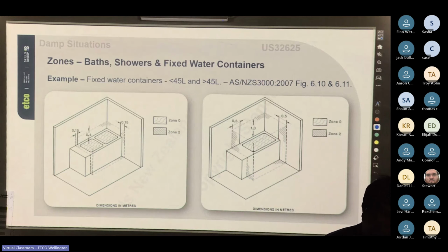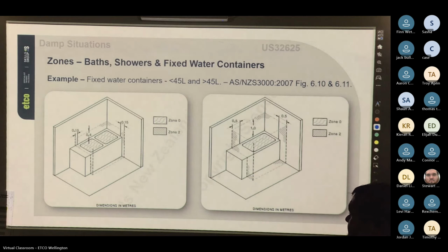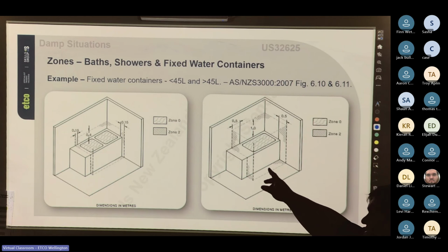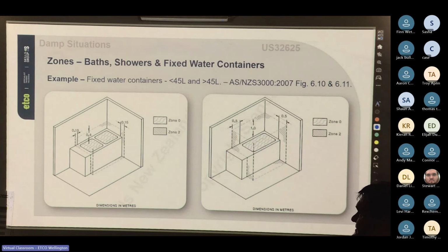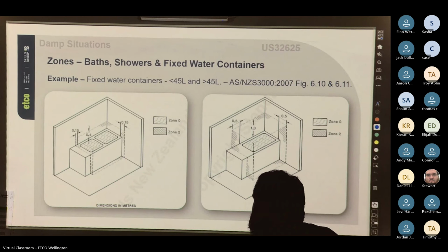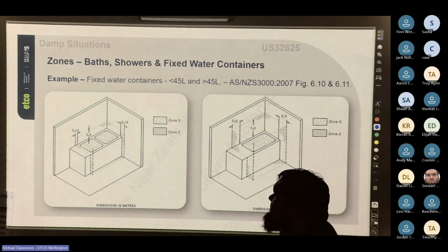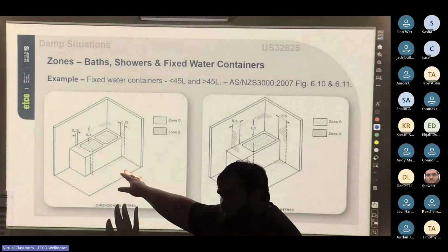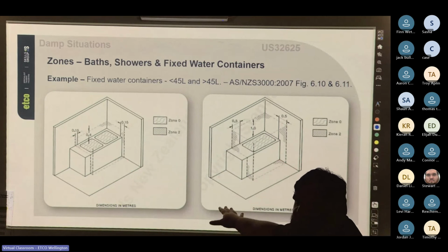The total amount of water held in one container. So not both of the containers, one container. Because if you look at those, they're both about the same overall size, but that one's divided in two. The reason for this is that if we hit the surface of the water in the one that's less than 45 litres, the splash would not be as large as if we splashed in the 45 litre or more. So it's all about how far the water could splash out. So when we have less than 45 litres, we can get closer. If we have more than 45 litres, we have to be further away.